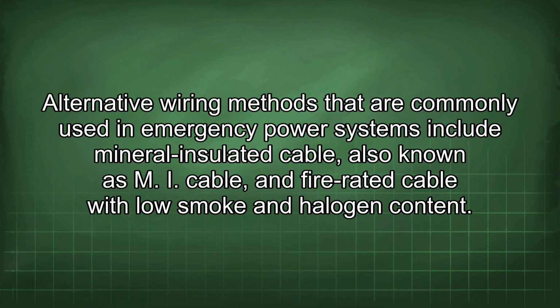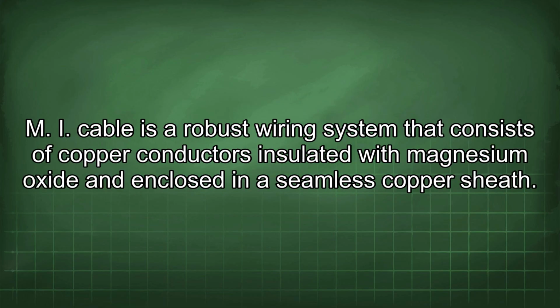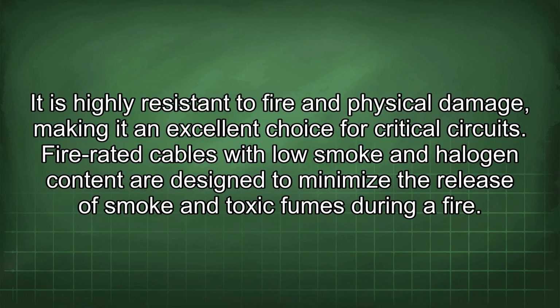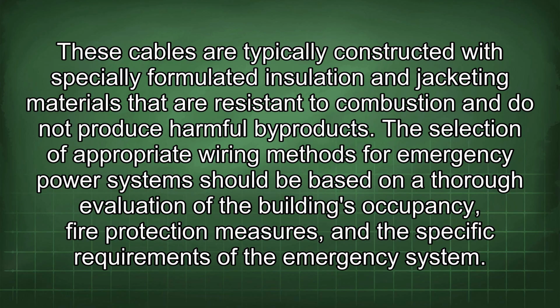Alternative wiring methods that are commonly used in emergency power systems include mineral insulated cable, also known as MI cable, and fire-rated cable with low smoke and halogen content. MI cable is a robust wiring system that consists of copper conductors insulated with magnesium oxide and enclosed in a seamless copper sheath. It is highly resistant to fire and physical damage, making it an excellent choice for critical circuits. Fire-rated cables with low smoke and halogen content are designed to minimize the release of smoke and toxic fumes during a fire. These cables are typically constructed with specially formulated insulation and jacketing materials that are resistant to combustion and do not produce harmful byproducts.